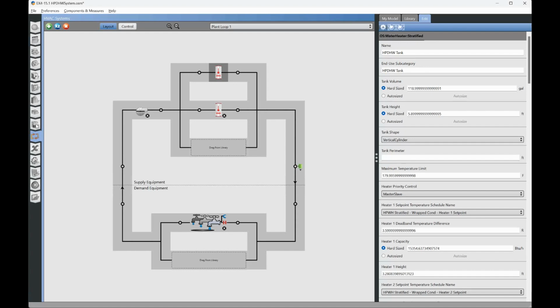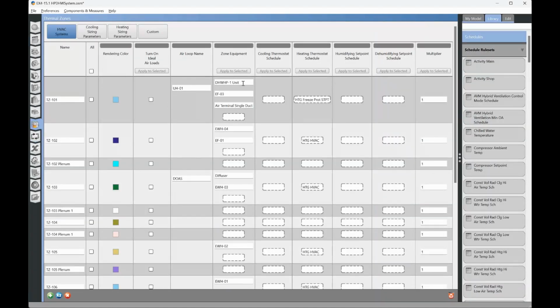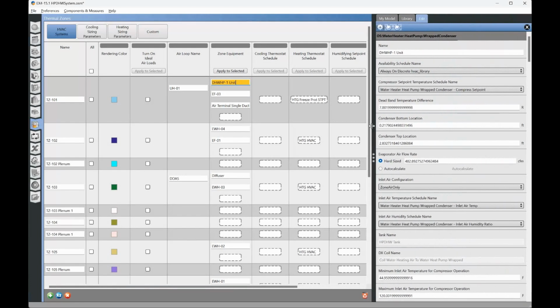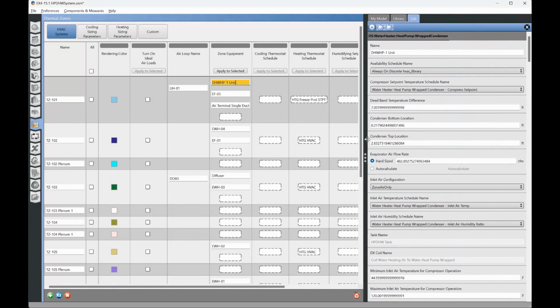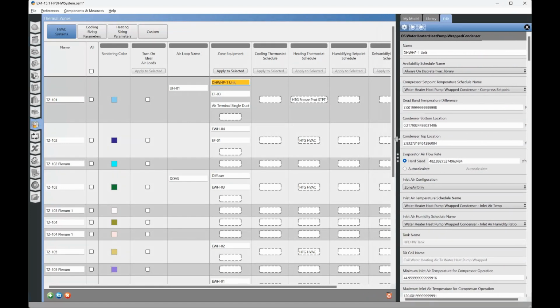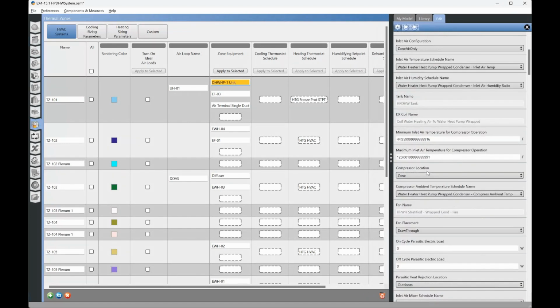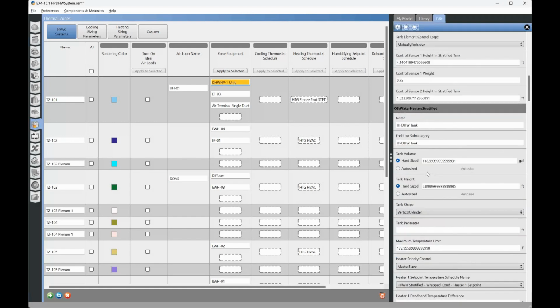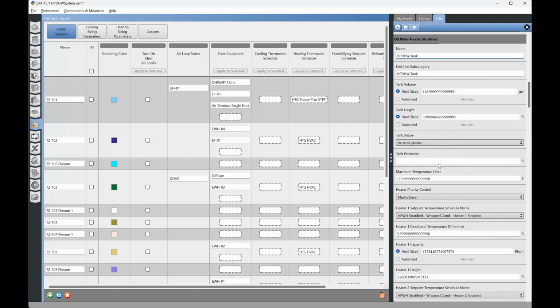So let's switch over to the thermal zone, and we'll select it from here. We'll have to scroll down to the tank that we were just working on. This is the tank. Maximum temperature limit. So heater priority control, there's two options here, master slave, or simultaneous.